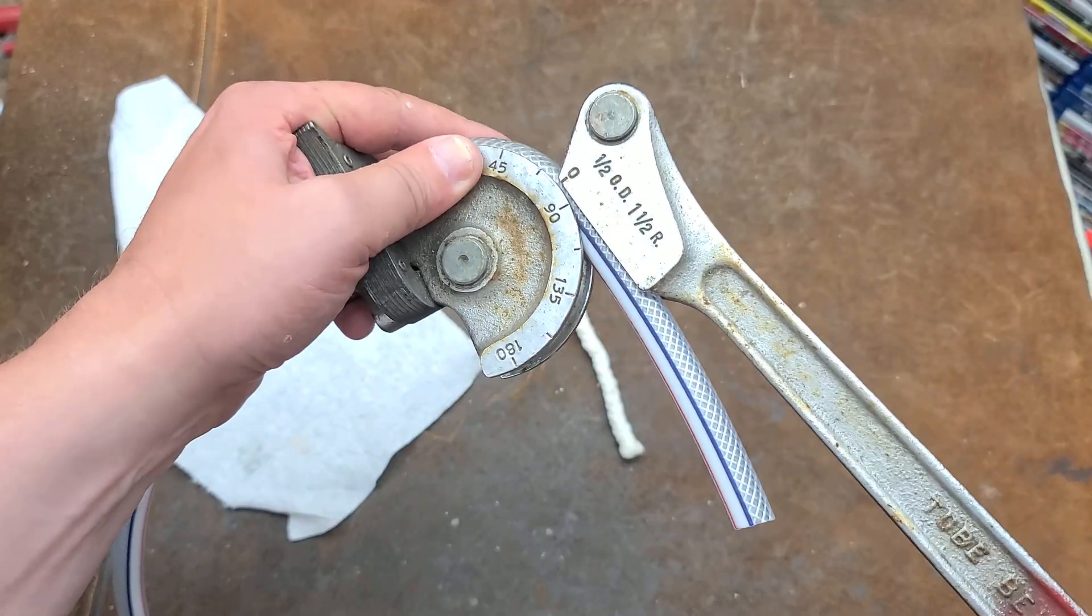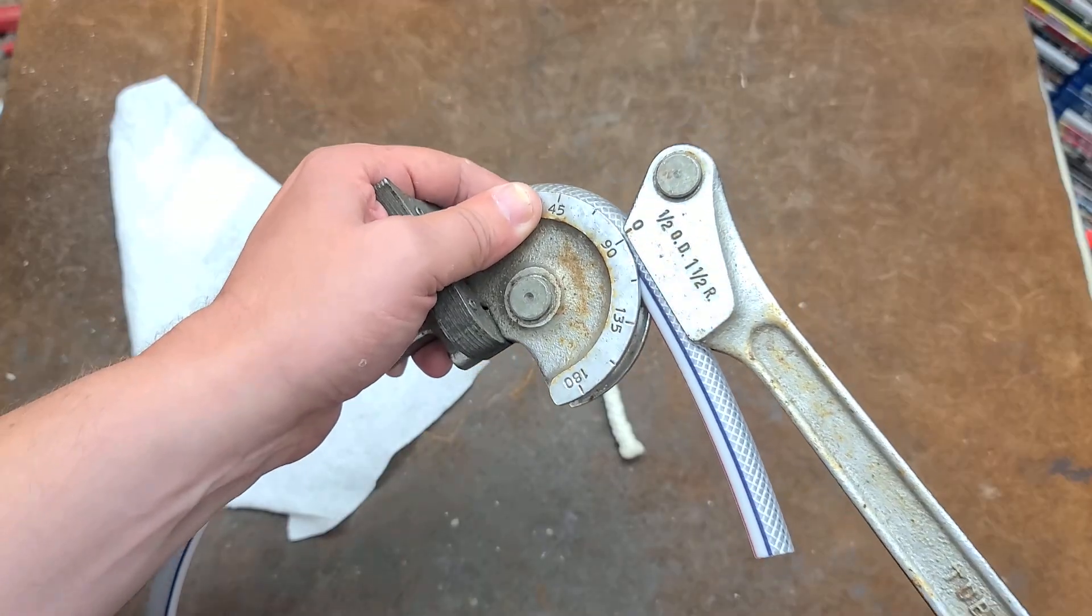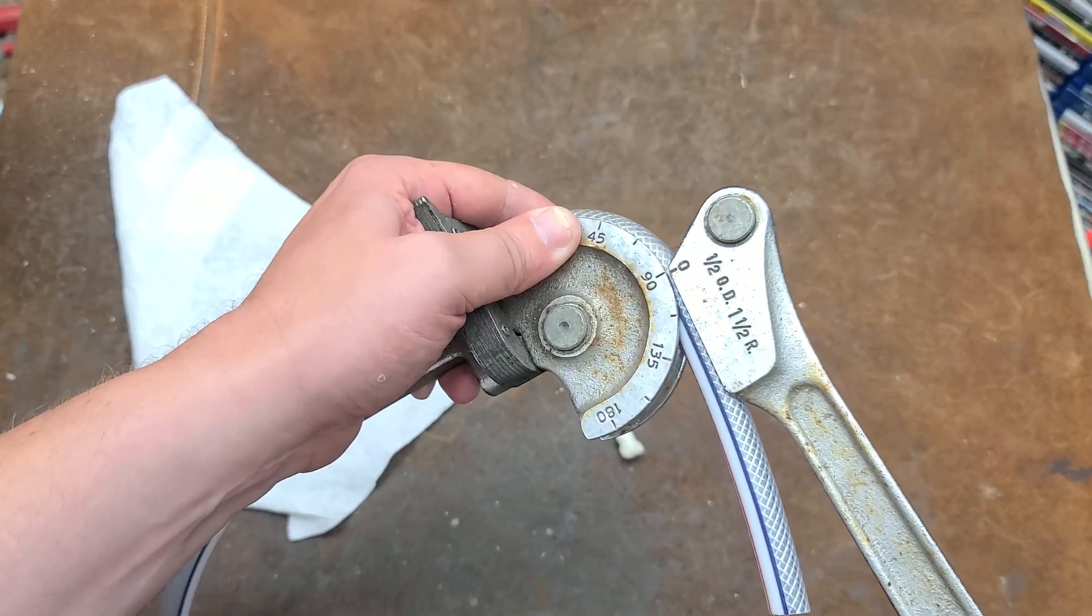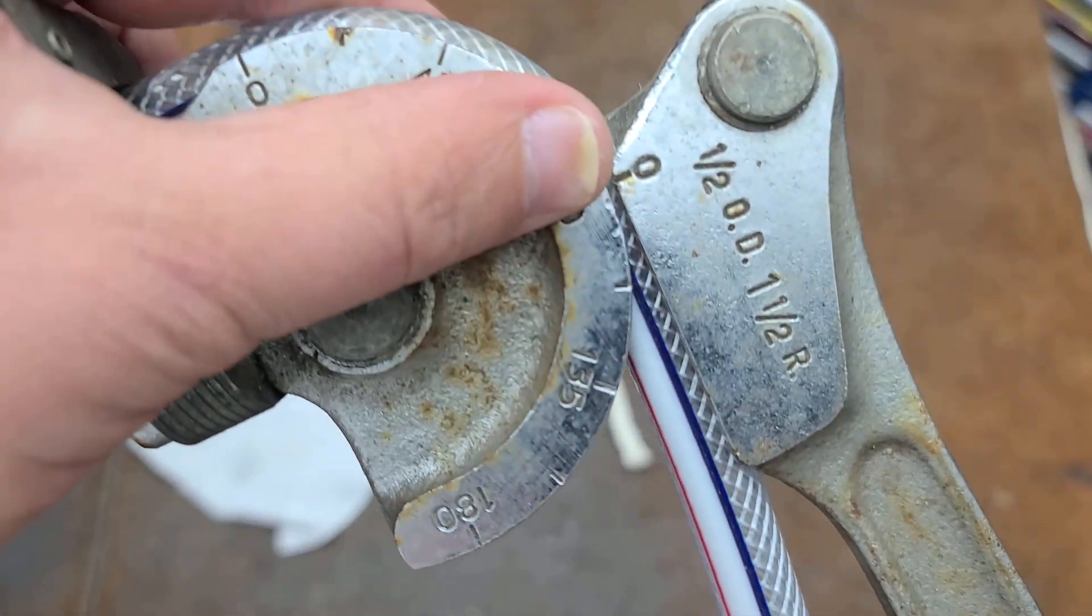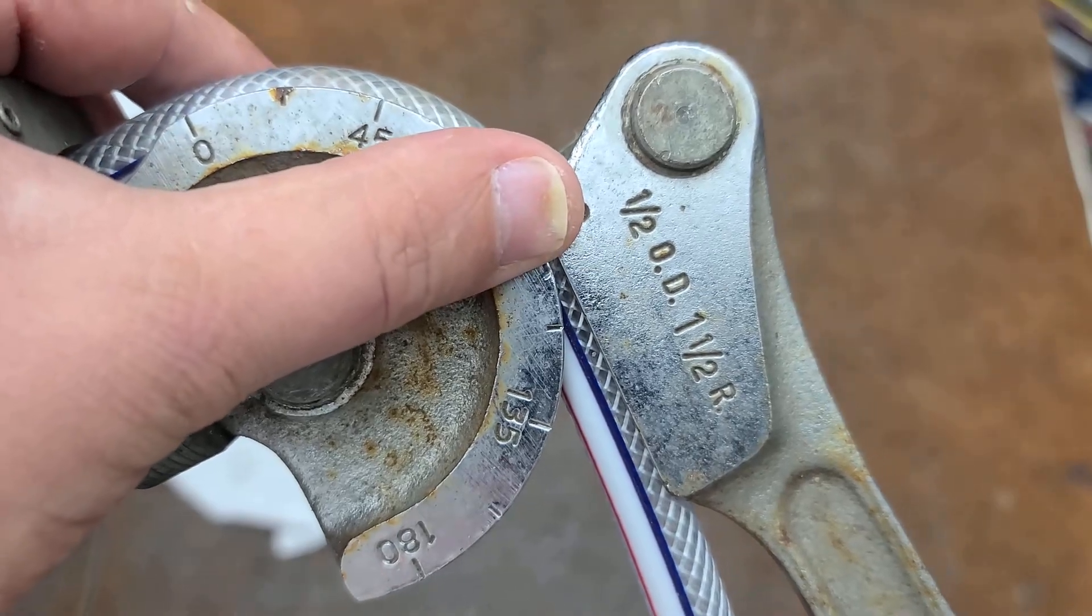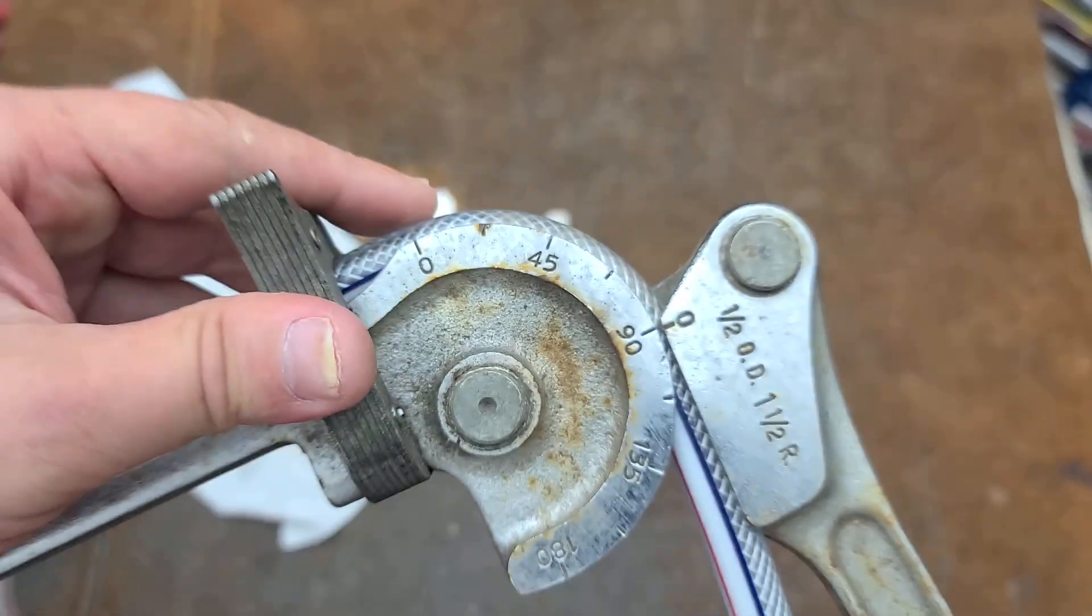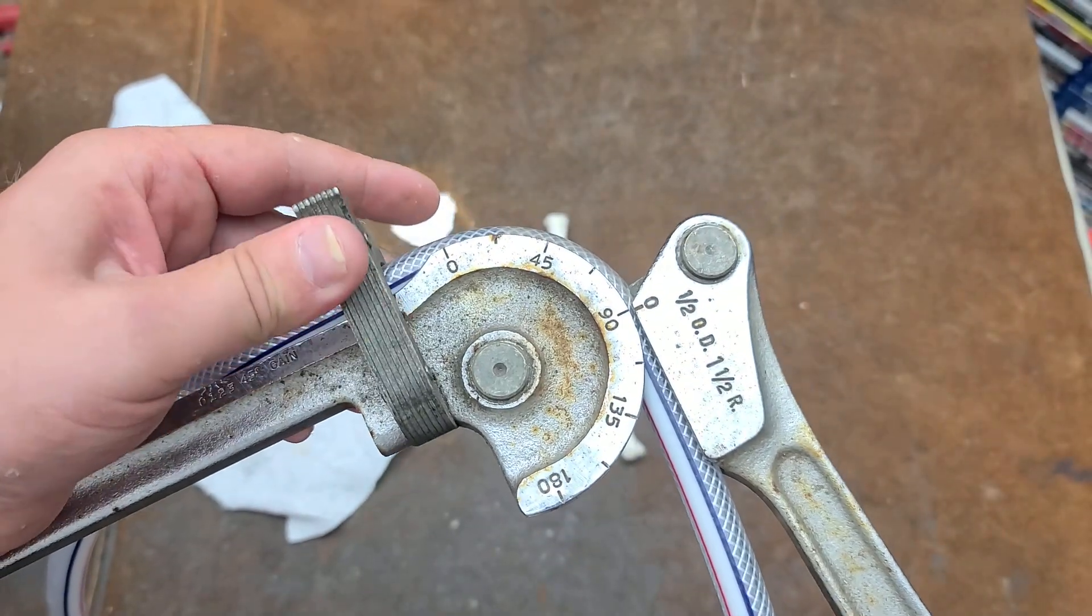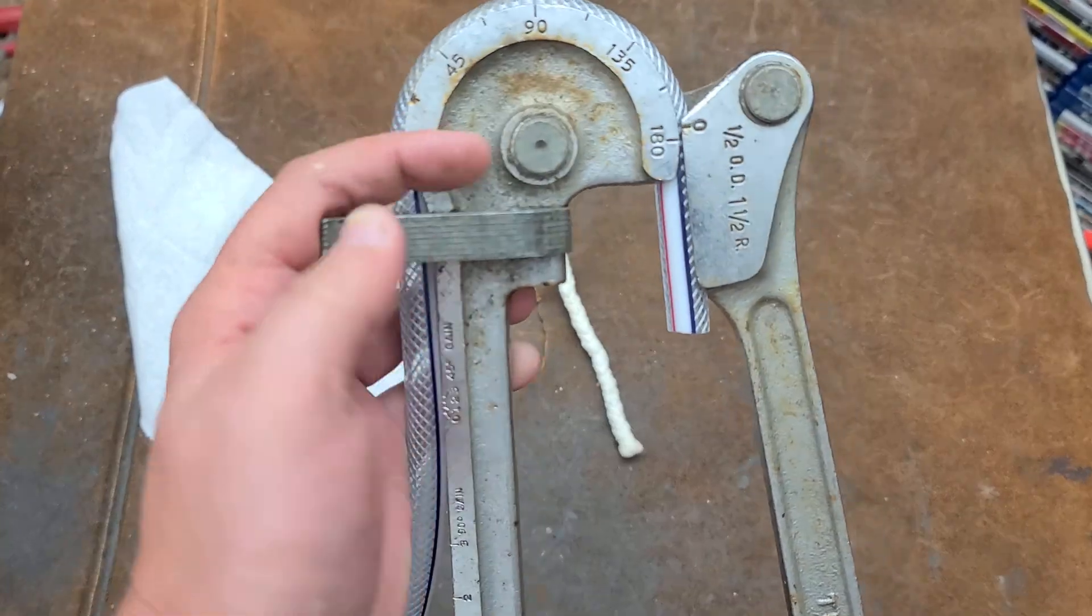This is what you use for refrigeration, air, water and that type of stuff. It's a half-inch outer diameter tubing, one and a half inch radius, which means if you do a 90 degree that will be a three inch circle across there.